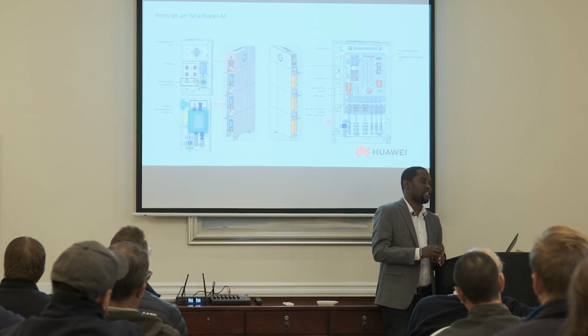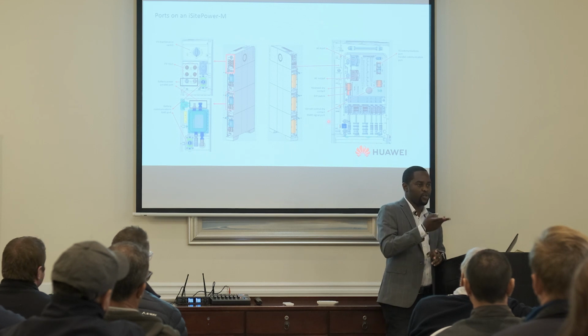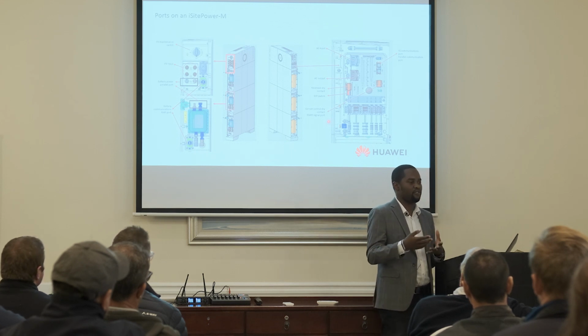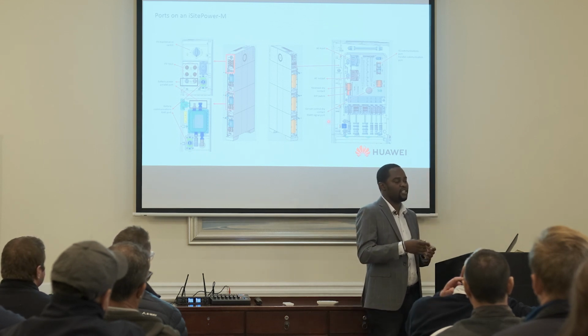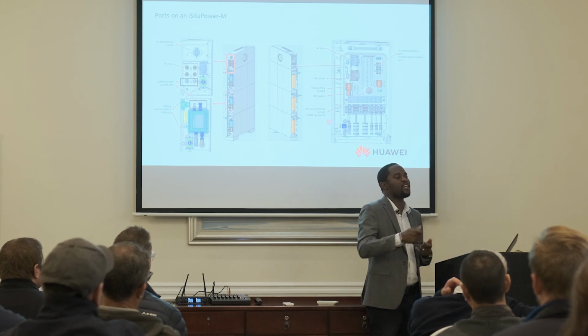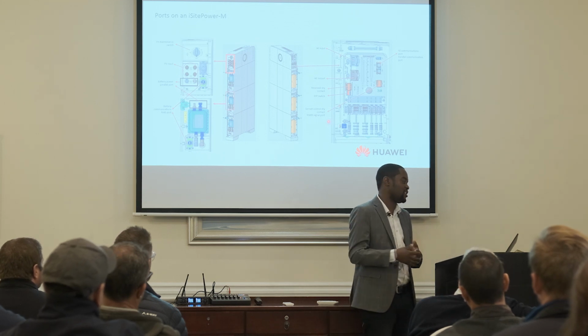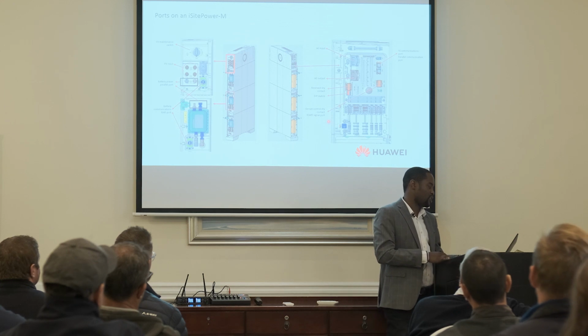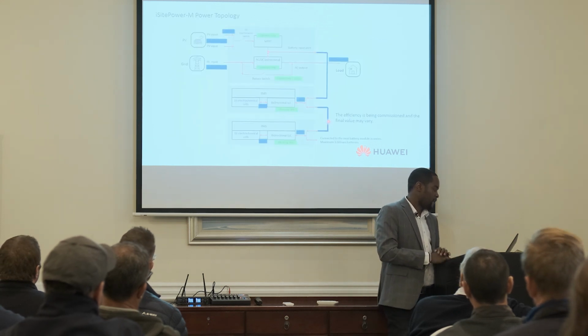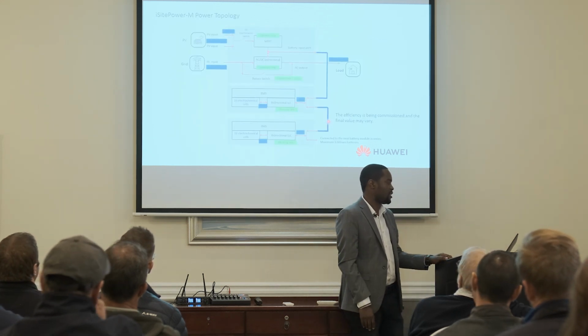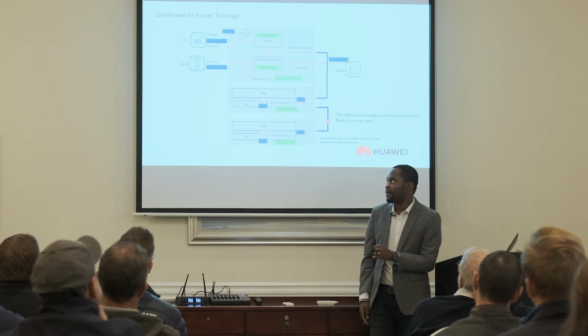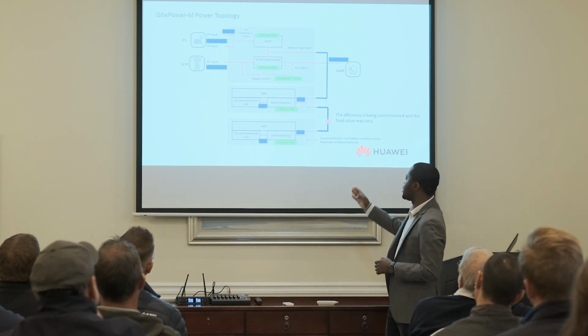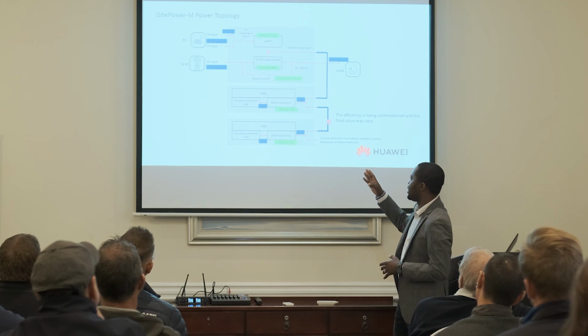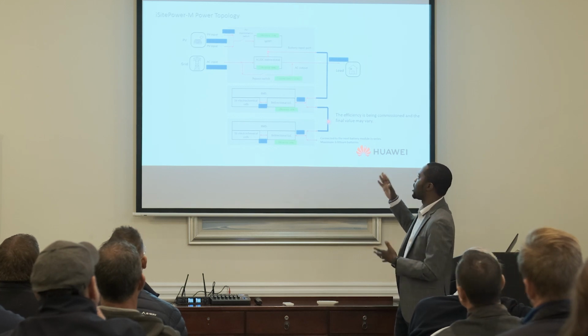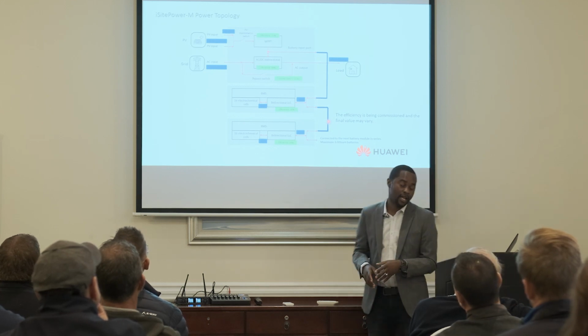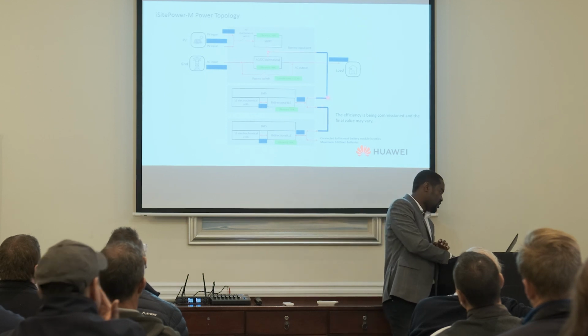But if you make a mistake on the batteries, then you damage your inverter. But it's impossible for you to make a mistake on the batteries if you don't go on site and clamp your own MC4s. If you are using the provided MC4s and the cables, then you can't make a mistake. They are high voltage systems, and this topology is just showing you that the batteries and the DC, or your strings or your panels, are going to the same bus bar, just like all the other inverters. So you see this is a common bus bar.